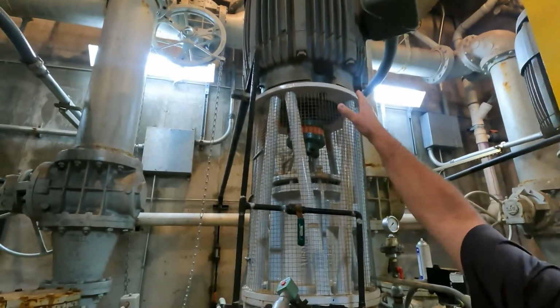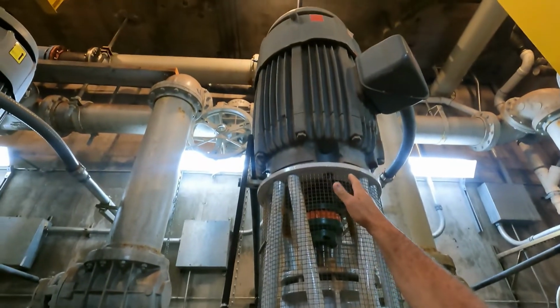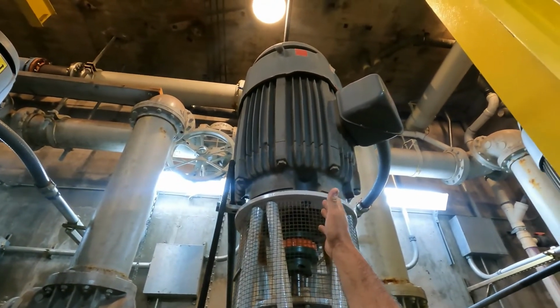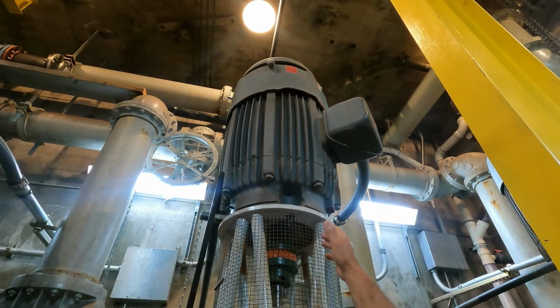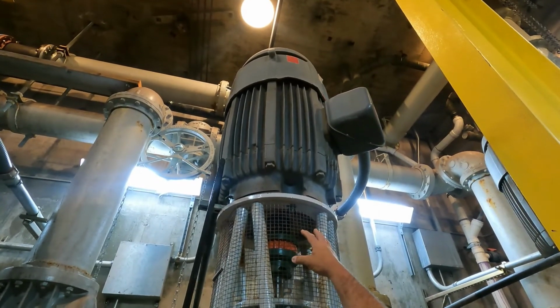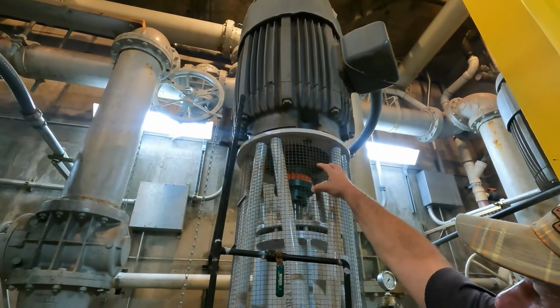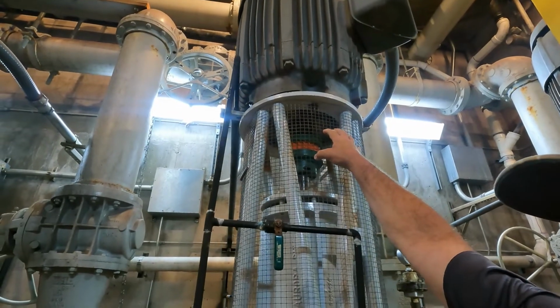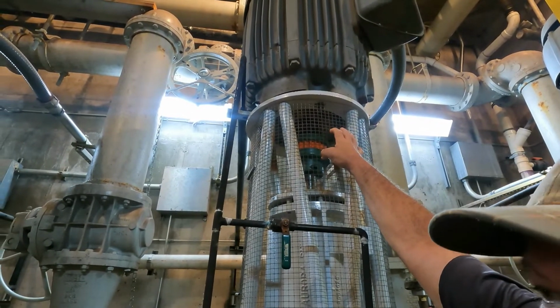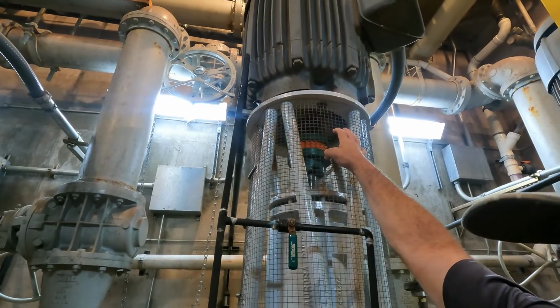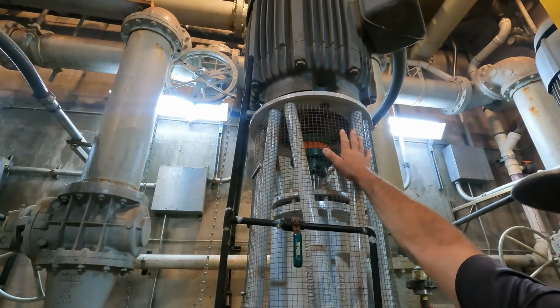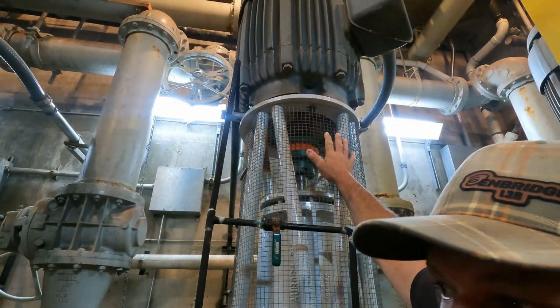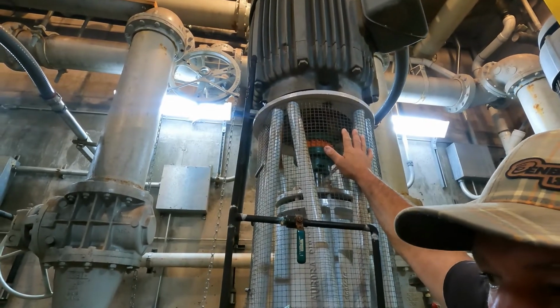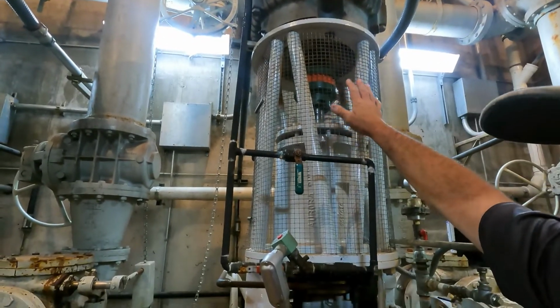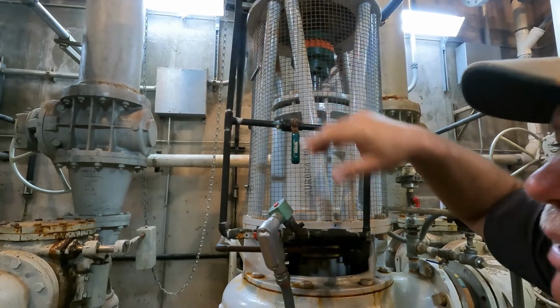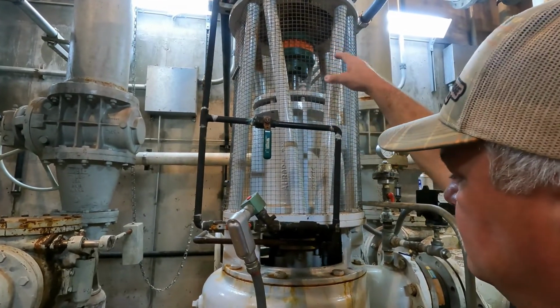So at the top of the pump, vertical shaft pumps. We got the motor that feeds it. These motors have to be 100 horsepower motors. Between the motor and the drive shaft of the pump itself is a coupling. So that coupling tends to be the weak spot. If something would come in and jam the pump, or if the pump is really out of alignment, then that would tend to chew up that coupling, and the motor would spin, but the pump wouldn't. So that would tell you that you have to service the coupling in between there, a flexible coupling shaft.